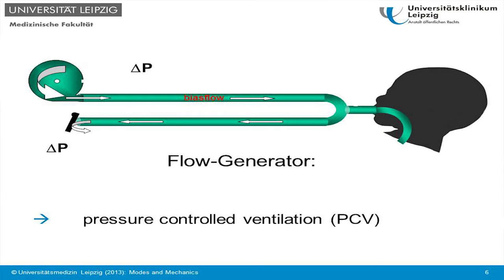Okay, so we have a flow generator here. The air goes through the tube along the patient and then to the exit valve, and the exit valve controls the pressure in the system, and when the pressure is higher in the system than in the patient, then we will get an inspiration. So this is called pressure-controlled ventilation, and has probably not much changed in the last decades.